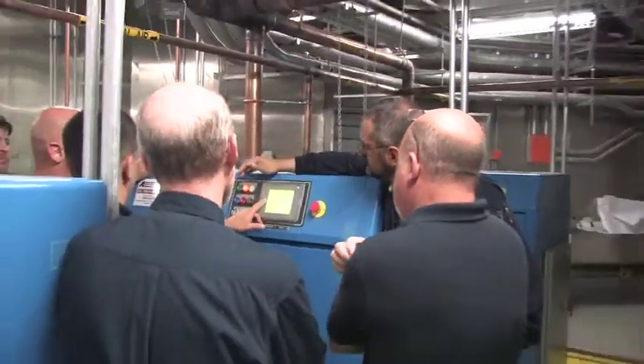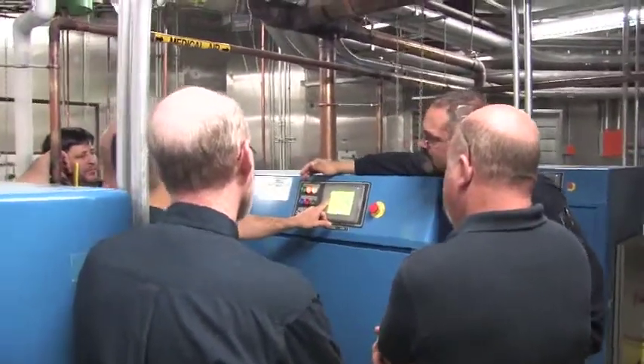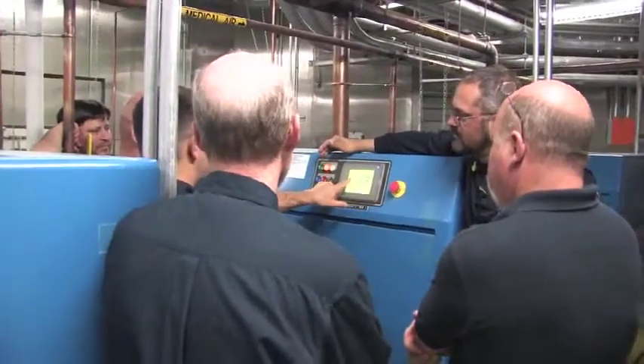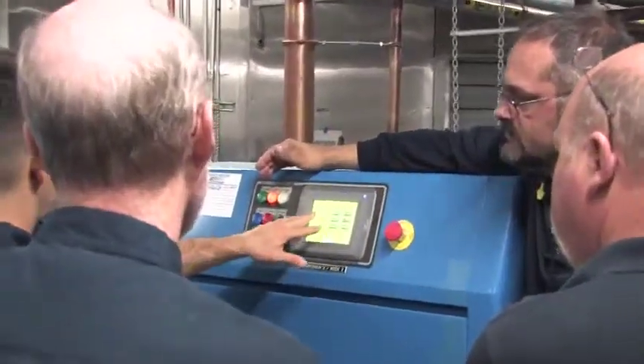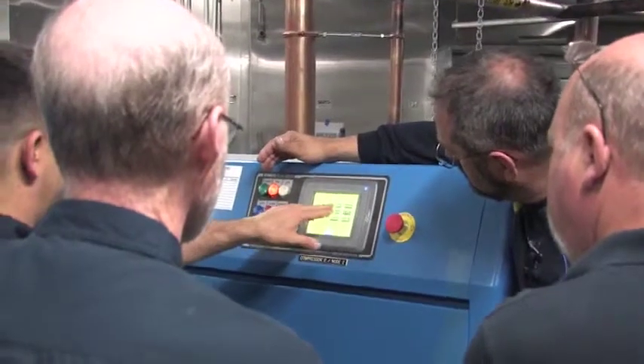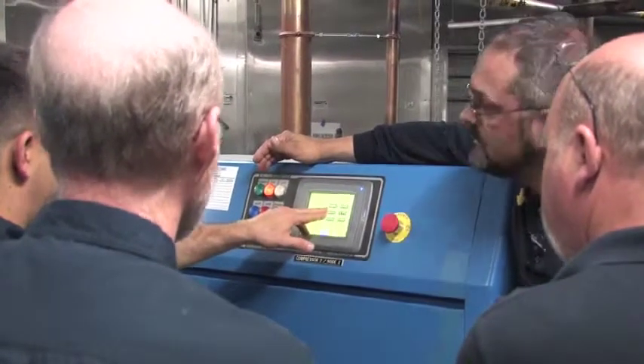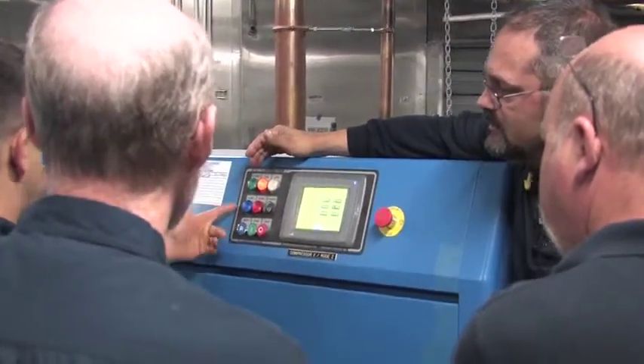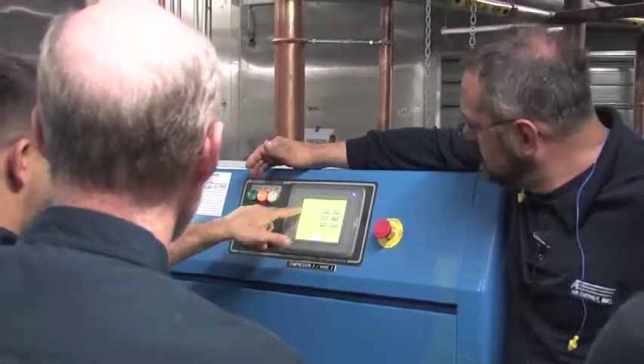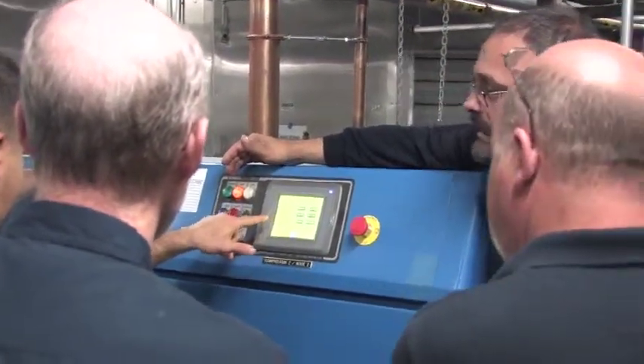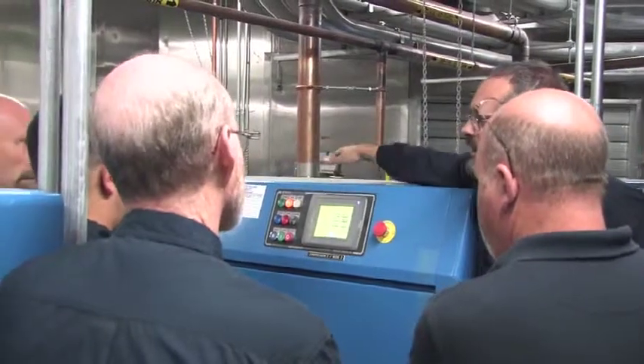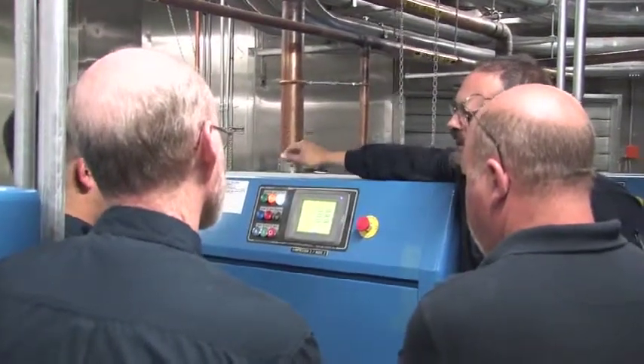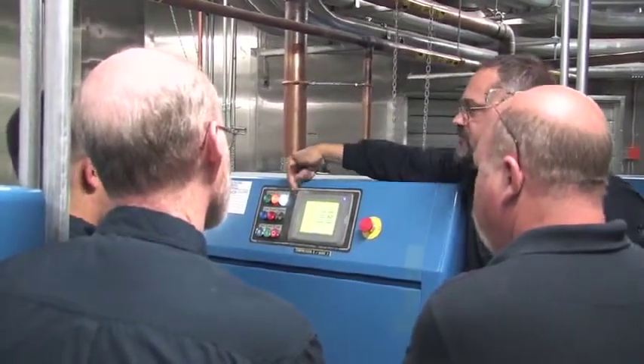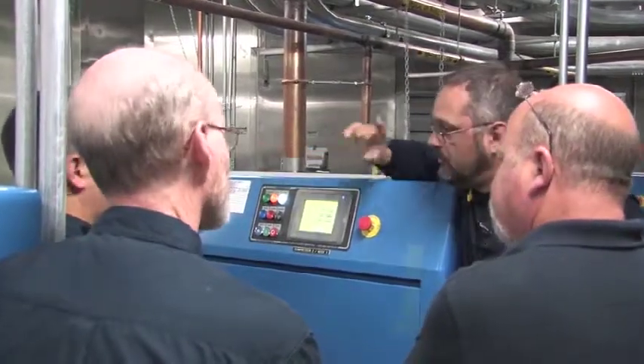Has there ever been an issue where the alarm comes in and everything looks like it's within parameters? You know what I mean? Like for instance, let's say this is 135 now, it alerts at 580. You come here, there's a high temp alarm, but this is still reading 135 at the time. Well, bear in mind, that's going to trip based on what it was. So if it tripped and shut down, everything cooled down, that's going to read whatever the temperature cooled to. So it'll start off to drop back down. Okay. Yeah. You'll know what your set point is.